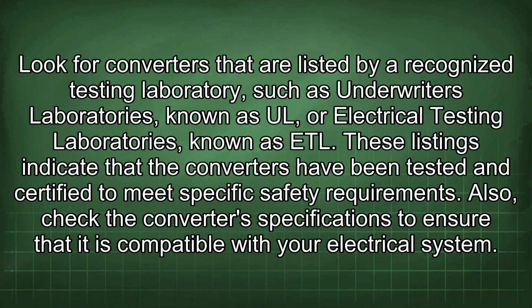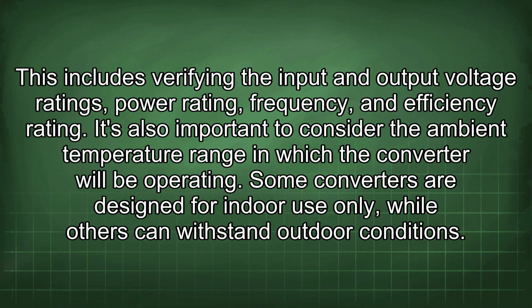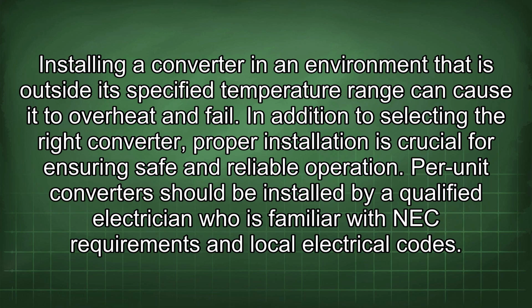Also, check the converter specifications to ensure that it is compatible with your electrical system. This includes verifying the input and output voltage ratings, power rating, frequency, and efficiency rating. It's also important to consider the ambient temperature range in which the converter will be operating. Some converters are designed for indoor use only, while others can withstand outdoor conditions. Installing a converter in an environment that is outside its specified temperature range can cause it to overheat and fail.